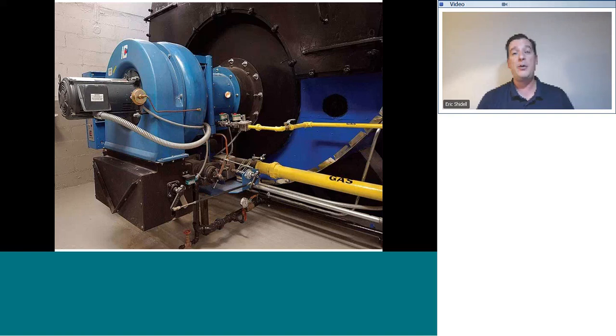That is a standard startup procedure for a very large burner like this, which is an on-off type of burner. Other burners may be modulated, so that once they have established flame, they can modulate these dampers and valves back and forth to give more or less fire, but that is not as common. Most of these burners, even though they look like they have the ability to be modulating, generally are an on-off or an on-low, high-off style burner, a two-stage or an on-off style burner.